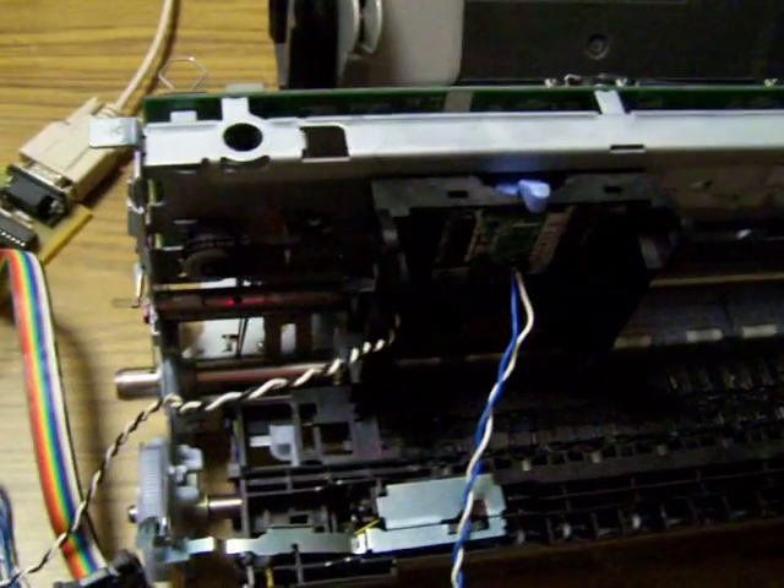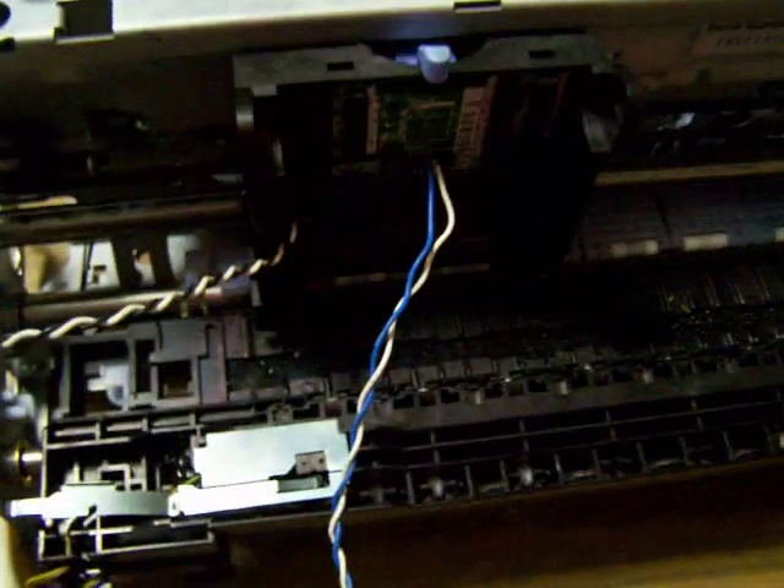There's a little bit of tuning needed — there's no PID setting yet. I've set it all fairly conservative, but this is just a test to see how stable it would be. It's fairly good and holds pretty well. It's fairly firm, but the P setting is not done yet.